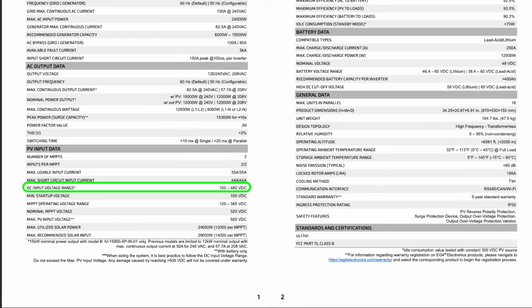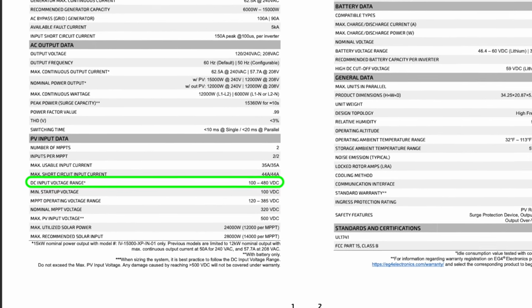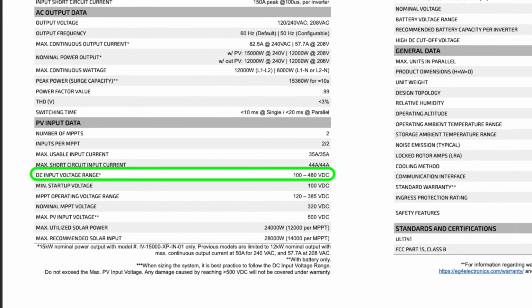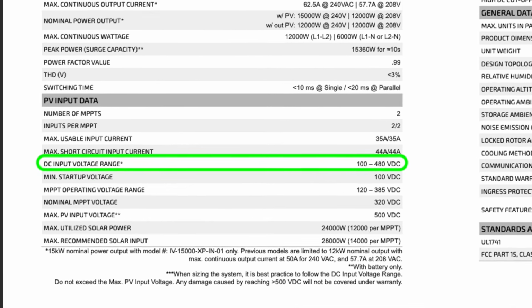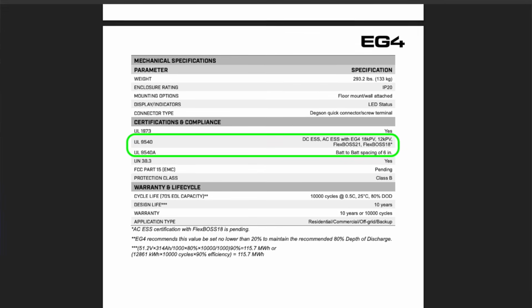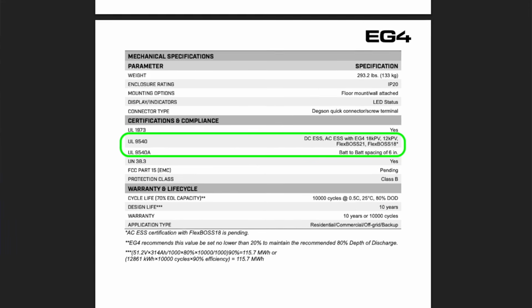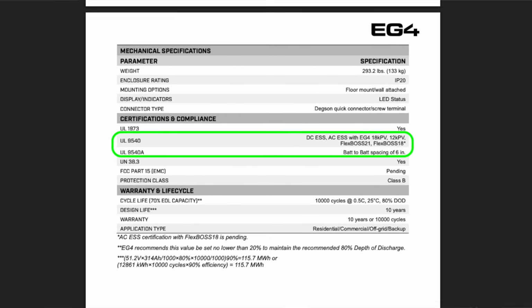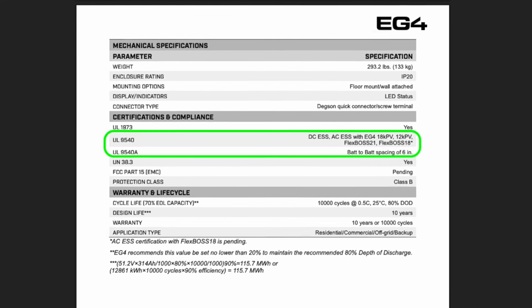Each input has up to 480 volts DC, which really gives you the ability to string up lots of solar panels in series and reduce the wire sizes and the wire runs from the solar panels to your inverter, which really is going to save you a lot on cost and complexity when you're installing this system yourself. So this inverter is UL listed, which means you can get it permitted and inspected in most jurisdictions.